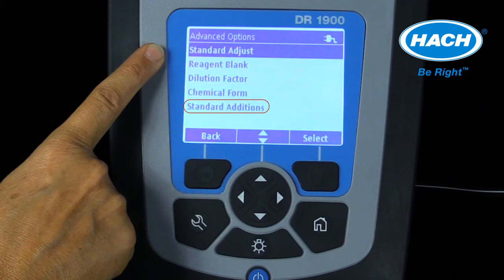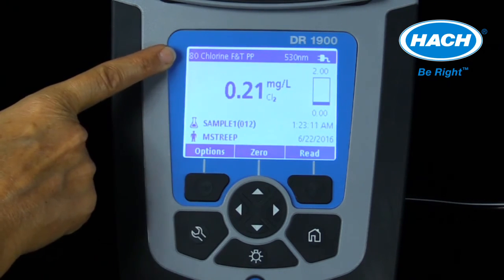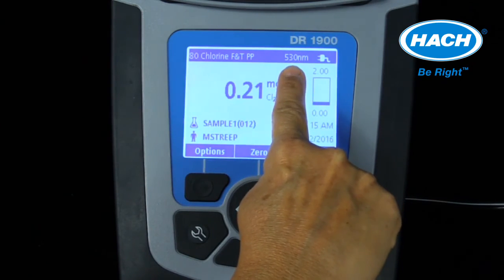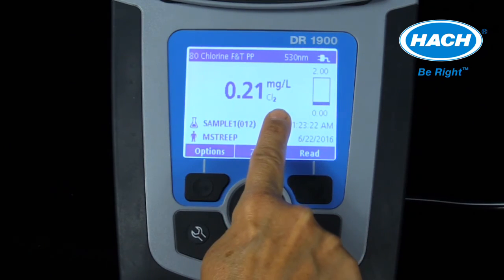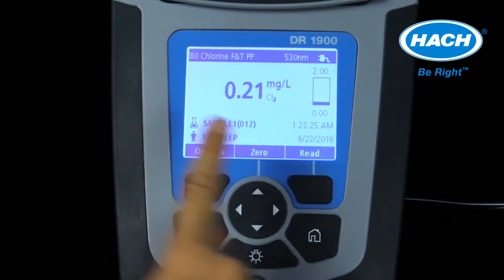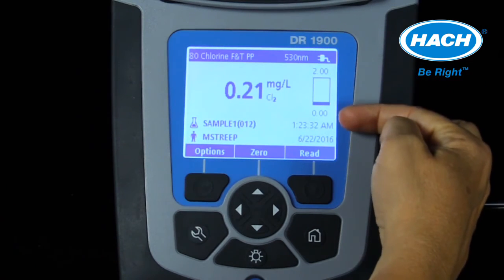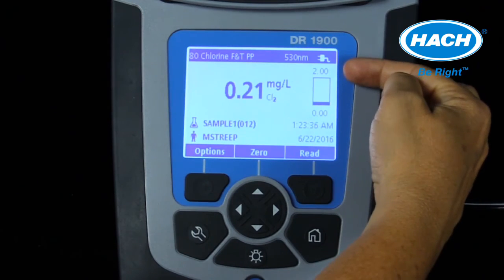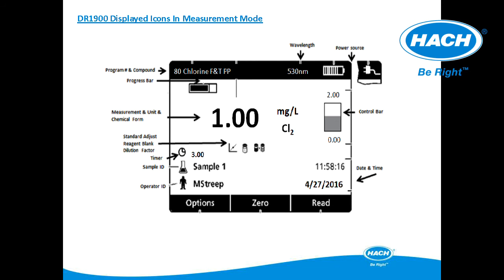Refer to the program's method written procedure for more information on this setting. The DR-1900 displays the same measurement information as the DR-3900 and DR-6000 spectrophotometers. Information includes program number and parameter, wavelength and power source, the measurement value, concentration and units, the sample ID and operator ID, and date and time. The control bar feature on the right-hand side of the display shows where this measurement resided within the total concentration range of the program. This slide depicts all the icons that can be displayed during a measurement and all the features of the DR-1900 software.